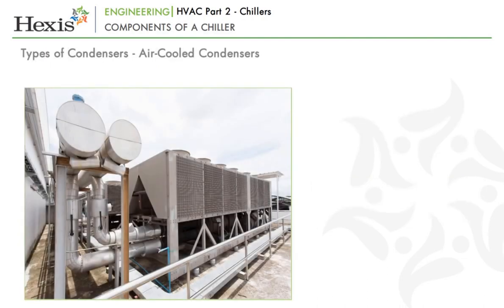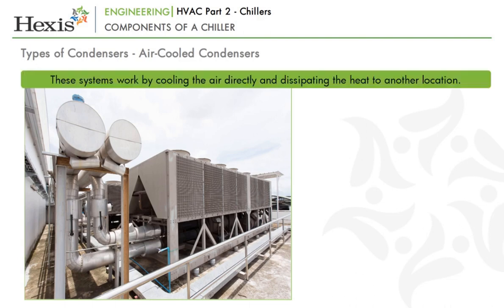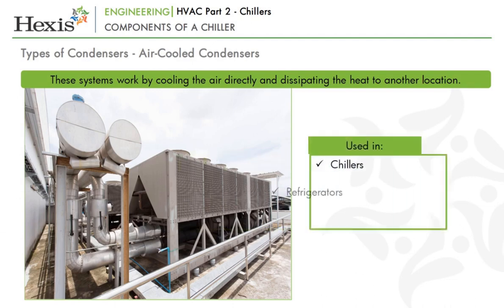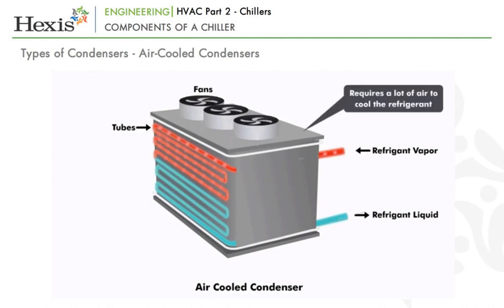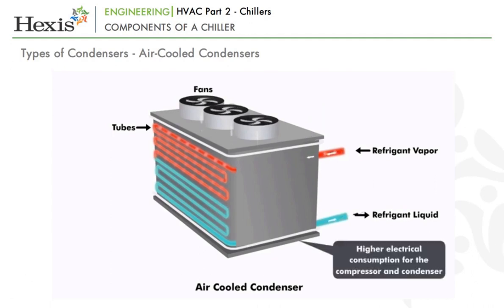Air-cooled condensers work by cooling the refrigerant directly and dissipating the heat to another location. They are widely used in chillers, refrigerators and air conditioning systems. The refrigerant passes through tubes attached with fins and is directly cooled by the air passing over the tubes, directed by a fan. Air-cooled condensers require a lot of air to cool the refrigerant and still do not lower the temperature to the levels achieved by water cooling. As a result, the electrical consumption goes up for the compressor as well as the condenser.